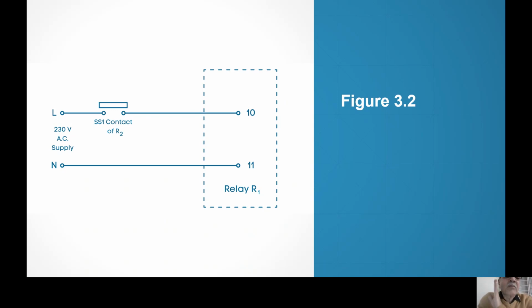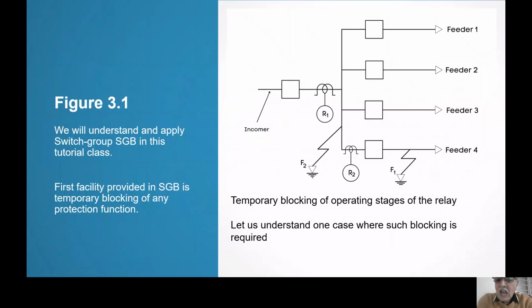This is what I do, automatic blocking. Once relay R2 starts, R1 is blocked. Right? And if R2 operates, then that start is gone. Then blocking is gone, right? Try to understand that R1 is going to operate. R2 is going to operate after 0.1 second. So the start will also become open and the trip contact will also become open. So blocking of R1 is withdrawn. So blocking of R1 is only for a small temporary period, right?